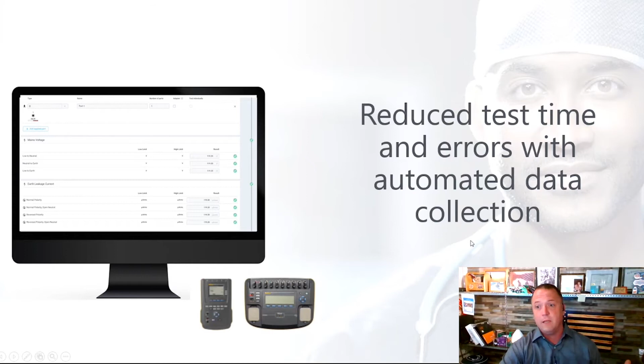Maybe you need to turn on the defibrillator or turn it off. Once you do that, you push the next button that says go, and it moves on and redoes all the testing for you. If you look at some of these new procedures, like the Zoll X Series defibrillator, there's a lot of tests that need to be done on it. So if you can automatically record this test while just pushing a button, keeping your hand on the device you're testing instead of moving from the device back to your analyzer, back to your PC—all those movements take up time.